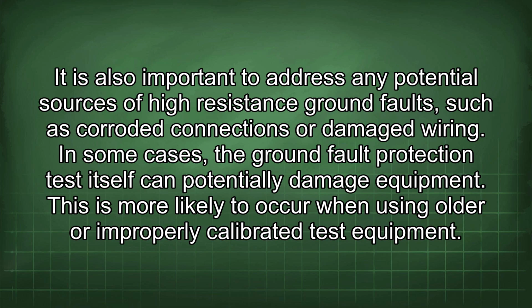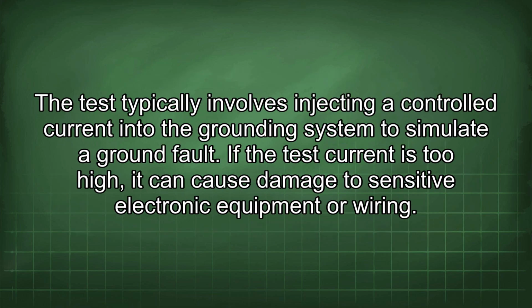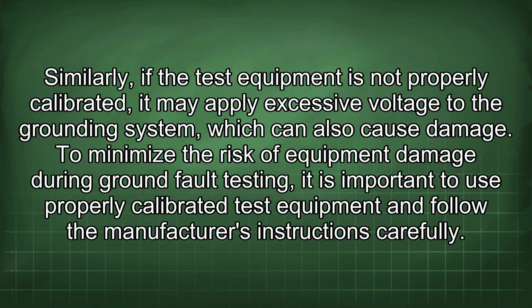In some cases, the ground fault protection test itself can potentially damage equipment. This is more likely to occur when using older or improperly calibrated test equipment. The test typically involves injecting a controlled current into the grounding system to simulate a ground fault. If the test current is too high, it can cause damage to sensitive electronic equipment or wiring. Similarly, if the test equipment is not properly calibrated, it may apply excessive voltage to the grounding system, which can also cause damage. To minimize the risk of equipment damage during ground fault testing, it is important to use properly calibrated test equipment and follow the manufacturer's instructions carefully.